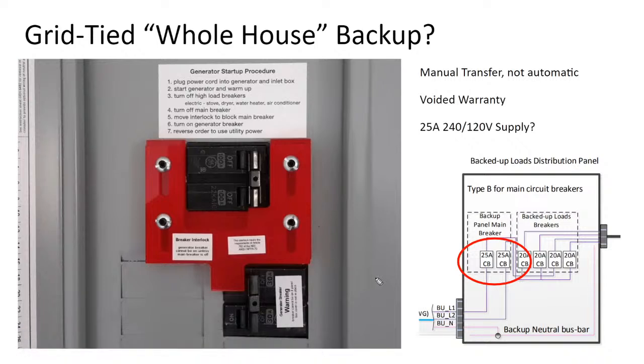One thing you can do if you want to power your whole house off a small battery backup inverter is take the critical load side and put it on a manual transfer switch. The cheap way to do it is called an interlock switch, which makes sure that only your main breaker or the backup generator can be on at the same time. So if you're limiting your whole house to just the 5 kilowatt draw, you could run your whole house from the main panel using a generator interlock panel.